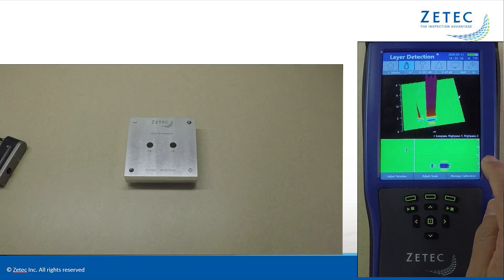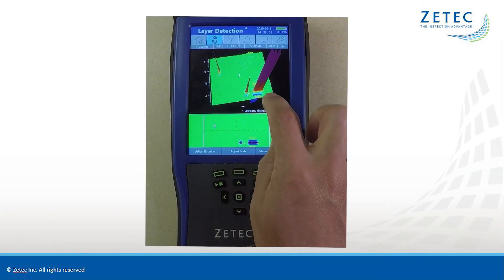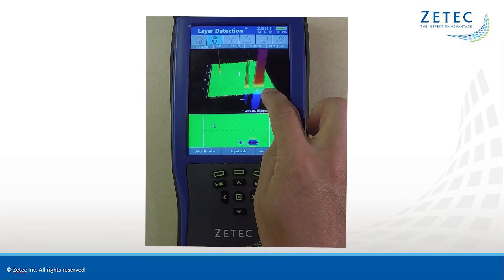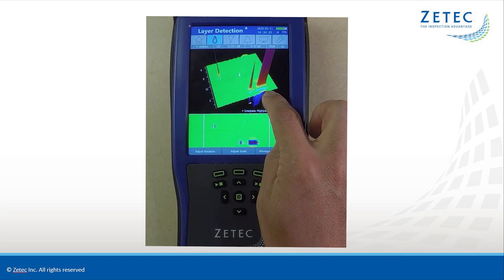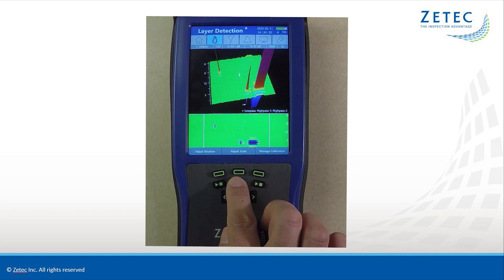The color C-scan display clearly shows the flaws and raises the probability of detection. It also reveals the different layers of the hole so you can easily determine which layer the flaw is located. There are no extra encoders or special equipment required.